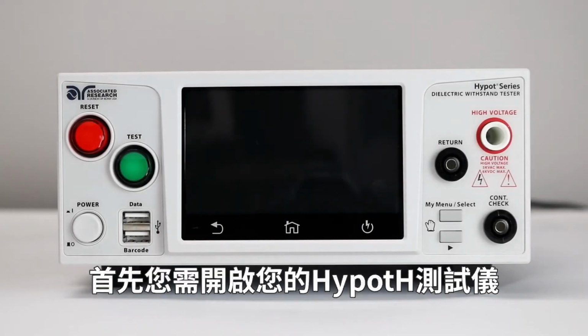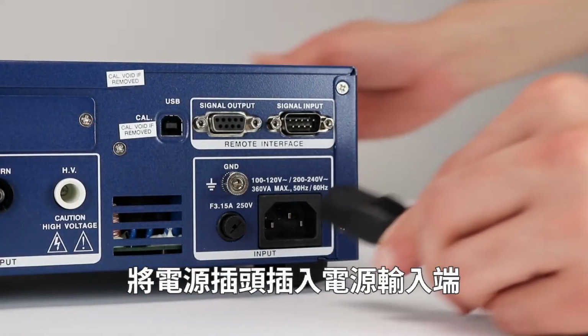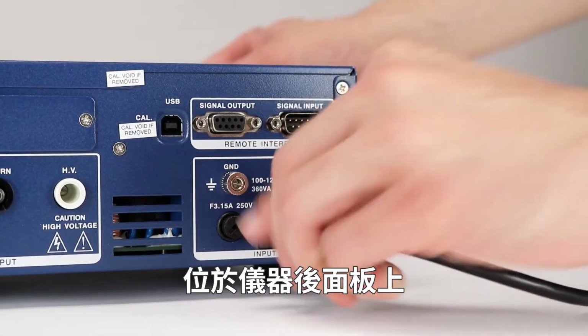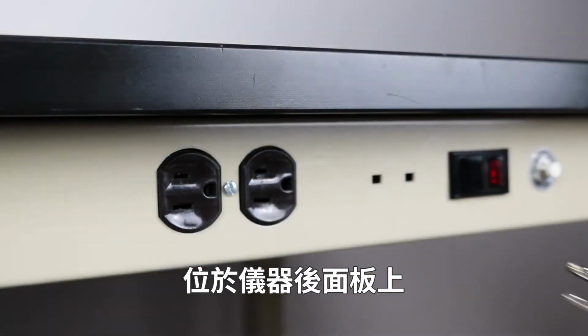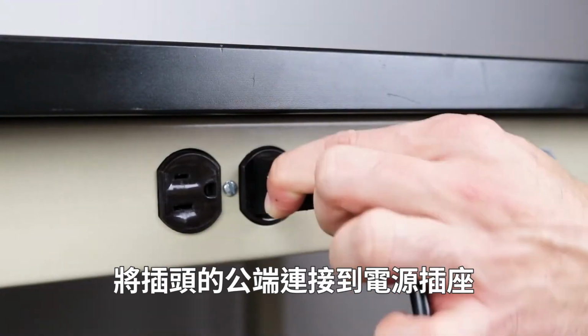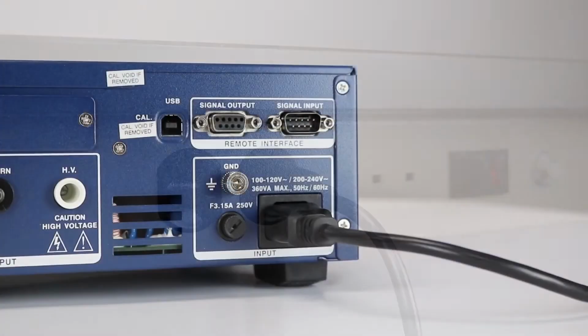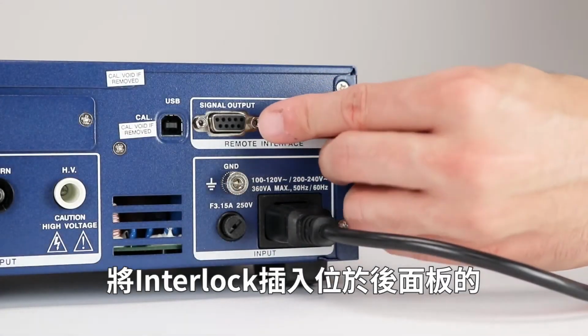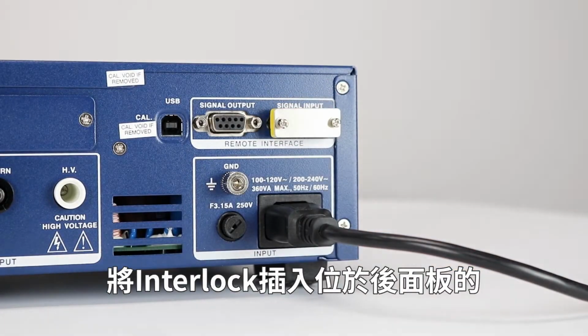First, you'll need to power up your Hypot tester. Connect the power input plug into its socket on the rear panel of the instrument. Connect the male end of the plug to the outlet receptacle. Insert the remote interlock key into the signal input terminal on the rear panel.